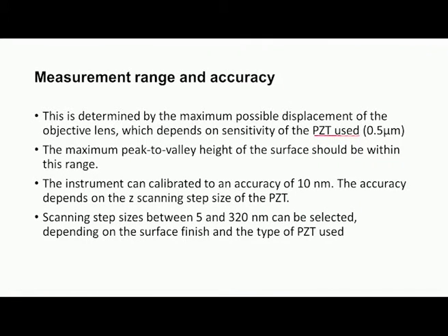Now, what is the measurement range and accuracy in such a system? The measurement range is determined by the maximum possible displacement of the objective lens. In other words, what is the maximum amount of movement of the PZT that is used. Typically 0.5 micrometer ranges are available, and the maximum peak to valley height of the surface should not exceed this range. That means, if we roughly know the peak to valley height, accordingly we have to select an appropriate profilometer which will accommodate that range. It is also very essential that we calibrate the profilometers with standard specimens, and these systems can be calibrated to an accuracy of 10 nanometer.